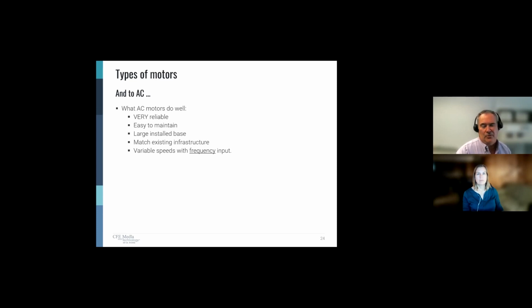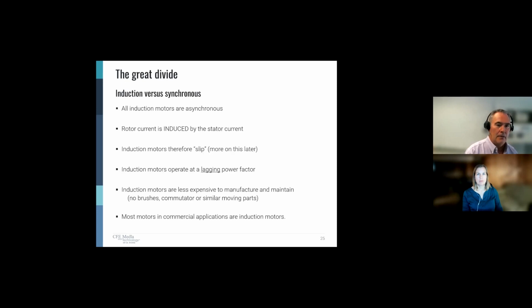The issue, if you want to call it that, is we vary the speed with frequency. And that is a little more complicated, which is probably why VFDs, or close control devices, took so long to develop. Within AC motors, and we're going to really focus on AC motors because most of us are working in the commercial building space, and even in industry and pump stations and water plants and wastewater plants, we're still all going to be AC type motors.